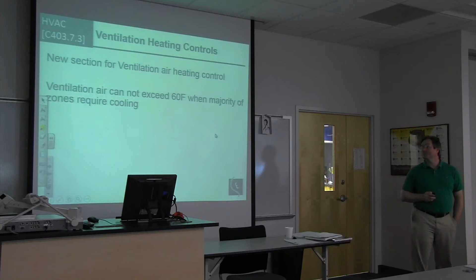And then talking energy recovery, this is one place where the code has gotten a little less stringent for 2018, where now for ventilation systems operating over 8,000 hours a year or nearly continuous operating, they provide you some de minimis allowance for ventilation air without having to do energy recovery on it. Where previously the limit was 0. The first CFM you moved had to have energy recovery on it.